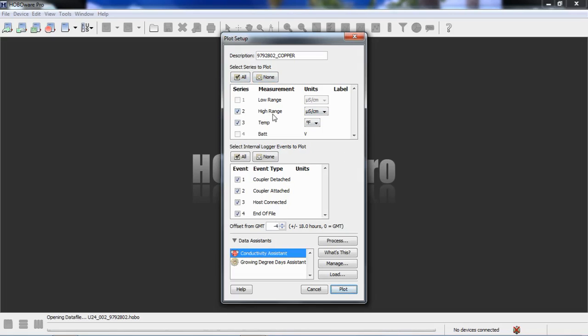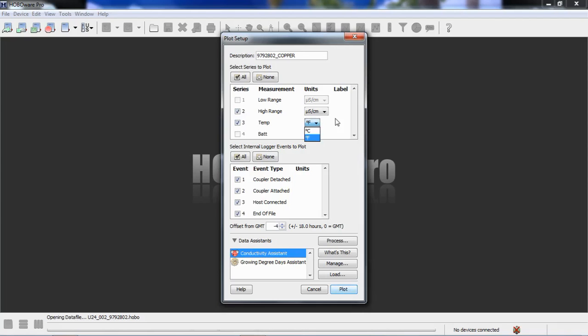We recorded data, conductivity data, in the high range only. You can see we can't click on low range because that was not recorded during this deployment. We also measure temperature, and we can choose to display this in either degrees F or degrees C in this plot. This doesn't change how the data was actually recorded in the data file. It's just for this plot, just for how we want to see it on our screen.